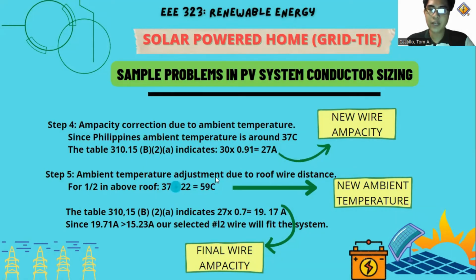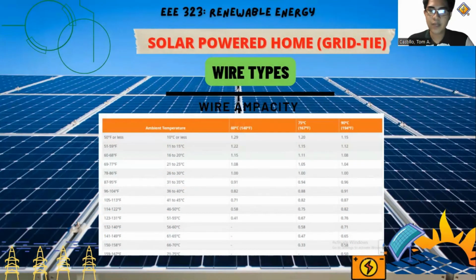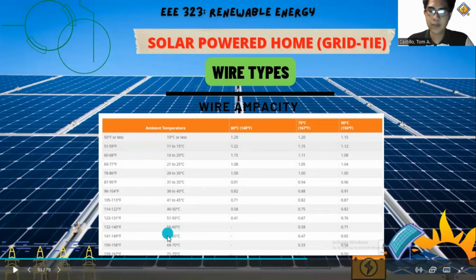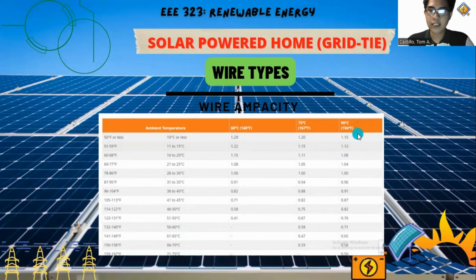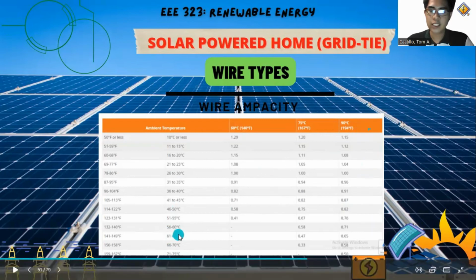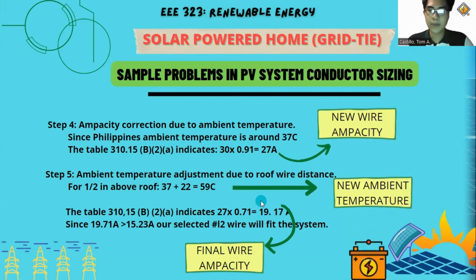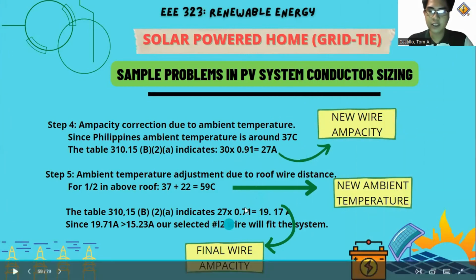So, dahil nabago yung ambient temperature, mababago rin yung capacity natin. So, ngayon dahil 59 degrees Celsius na yung ambient temperature natin, mababago na yung multiplier natin. So, dito, saan ba pasok yung 59 degrees Celsius? So, dito siya pasok sa 56 to 60 degrees Celsius. So, katulad niya kanina, dahil yung wire natin is 90 degrees Celsius, dito tayo mamimili. So, yung 56 to 60 degrees Celsius, ang magiging multiplier natin is 0.71. So, yung capacity natin na 27 amperes, ito times natin siya sa 0.71. So, bali ang magiging final wire ampacity natin is 19.17 amperes.